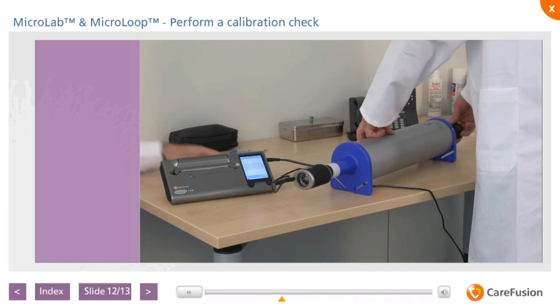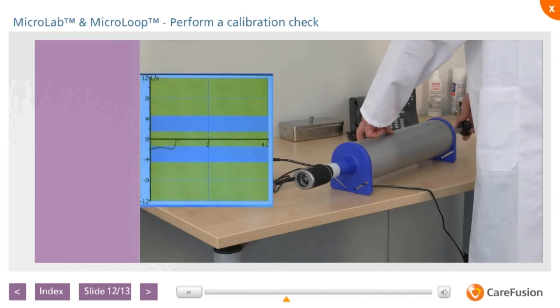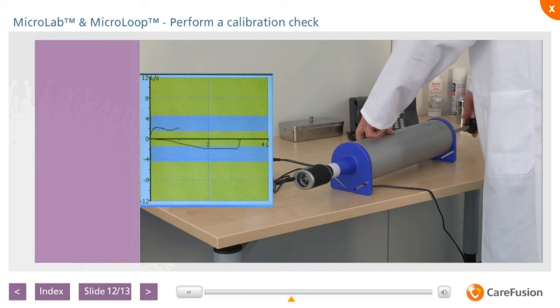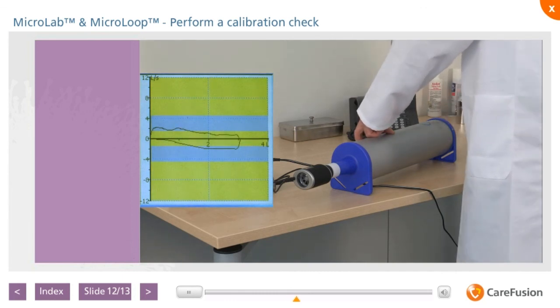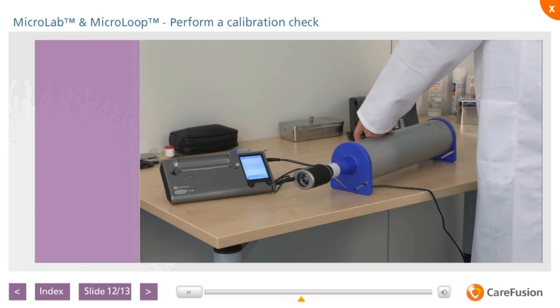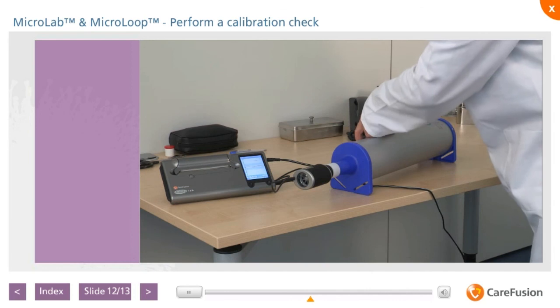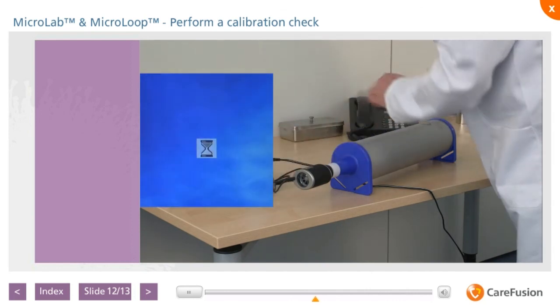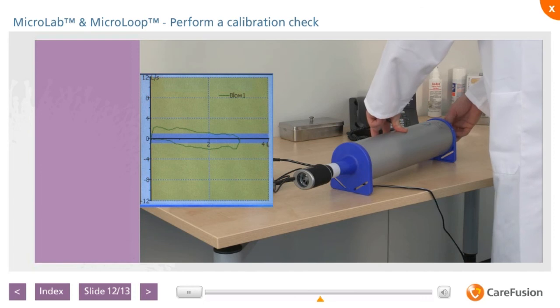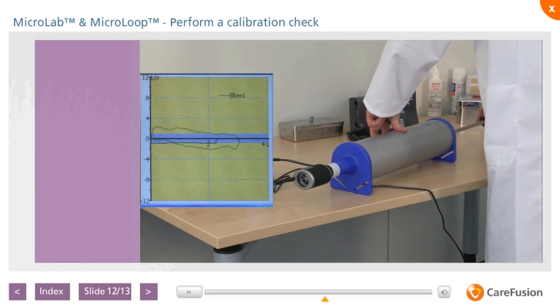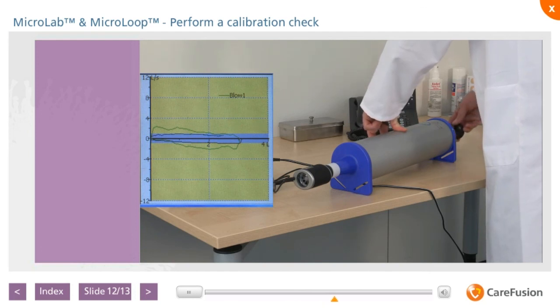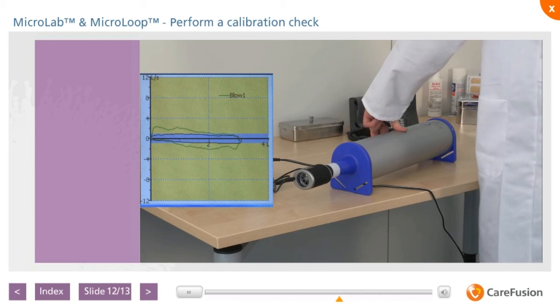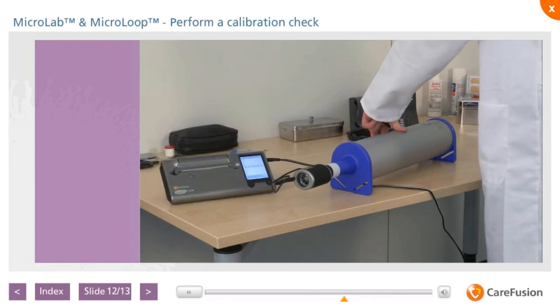The calibration check should be performed at 3 flow rates. The display will show 2 grey bands. These are for guidance as to the speed the syringe should be emptied and filled. When emptying and filling the syringe, the maneuver should be performed at a smooth, sustained speed, avoiding slowing or stopping during the maneuver. As per the instructions on the screen, empty the syringe by pushing the plunger in and then fill the syringe by pulling the plunger back out. The process can be repeated if necessary by rejecting the current maneuver and repeating.